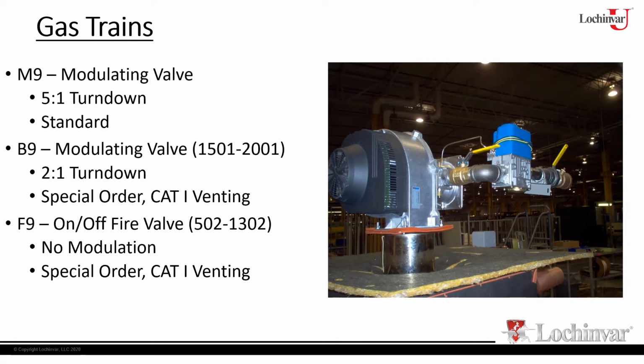This is a category 1 vented appliance. That means you're using B-vent, not category 4 stainless steel. So primarily you're going to use this in a retrofit where you've had a B-vent stack already established and you're going to go back with a B-vent unit. Now, because it's minimal modulation, my control looks at the flue temperature and it's going to control the modulation based on what the stack temperature is doing.